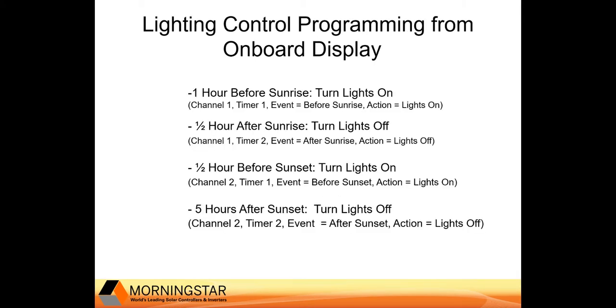In this slide, we're taking a look at the channels and the timers for the particular events we want to have happen. For turning the lights on in the morning, we're going to use channel one, timer one — the event is before sunrise and the action is turn the lights on. For turning the lights off in the morning, channel one, timer two — the event is after sunrise and the action is lights off. For turning the lights back on in the evening, channel two, timer one — the event is before sunset and the action is lights on. For turning the lights off in the evening, channel two, timer two — the event is after sunset and the action is lights off. When done programming these, we're going to want to combine these timers all as OR functions so they operate independently of one another.